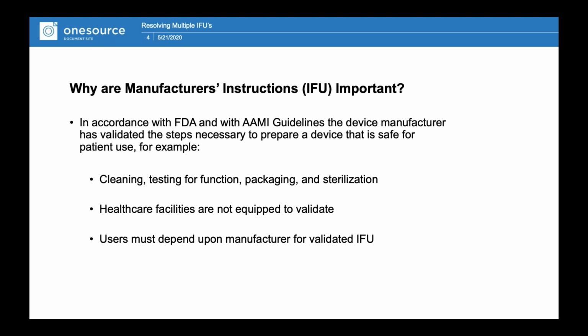Just as a word of caution, if you come off this webinar and then go diligently pick into your IFUs, you have to collaborate with your customers. If you discover that there's devices that need to come apart in the IFU, don't just start doing that, SPD. You have to collaborate with the OR. They may need some training. We can't send them up a laparoscopic or a robotic instrument in 100 pieces and they try to put it together in the OR. We kind of have to do some training and give them a little bit of a heads up on that. Healthcare facilities are not equipped to validate.